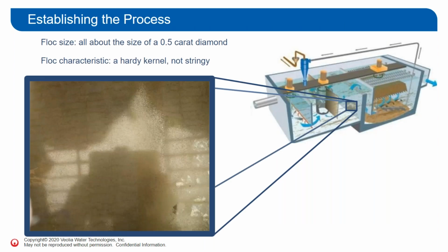So you can see a picture that I've inserted here taken from the maturation chamber, where Brian said the magic really starts to happen. You could see the light kernels of those flocs start to form, and more importantly, that darker interstitial water in between the two. So it becomes apparent here that we've got some good process happening, and this is what you want to see.